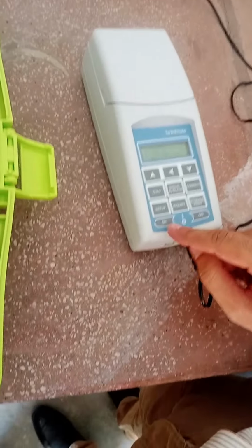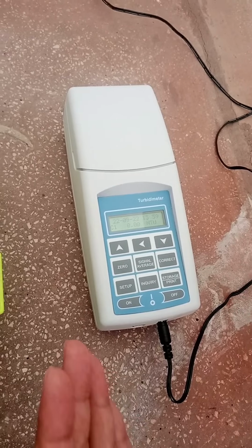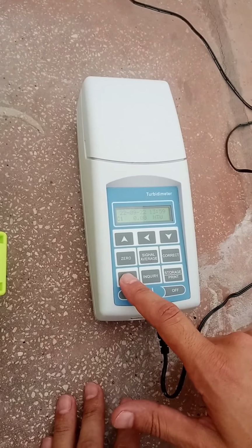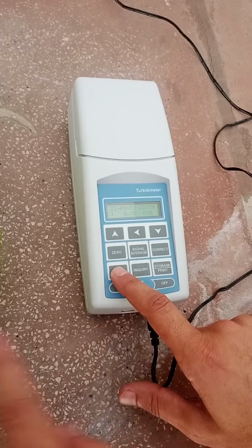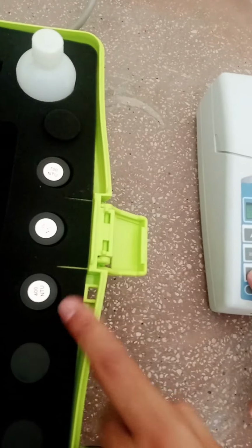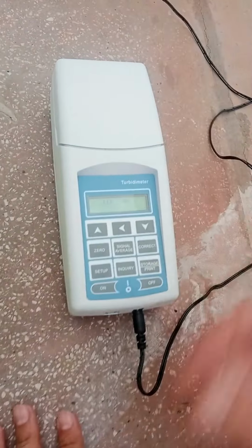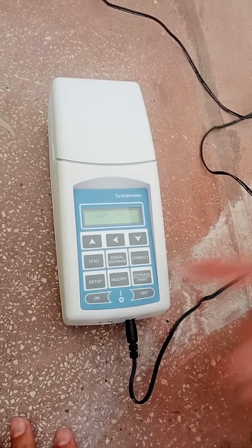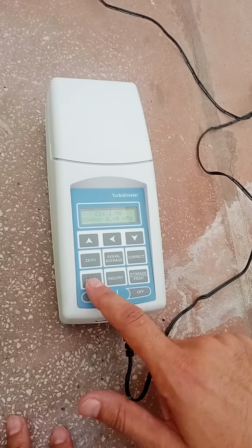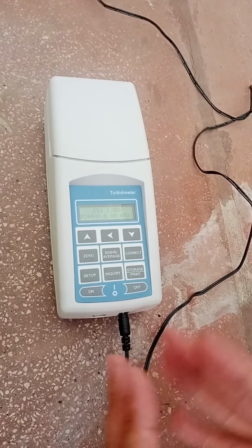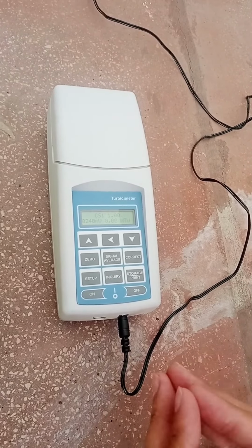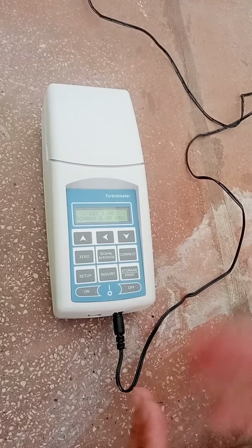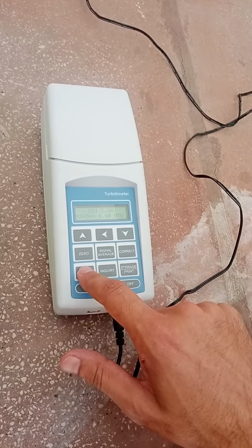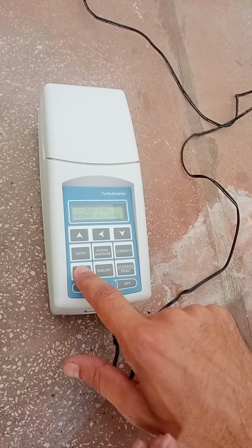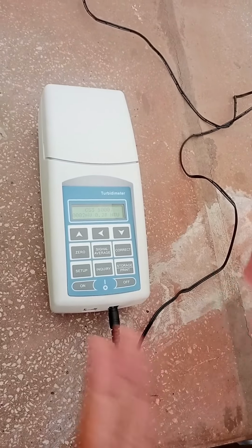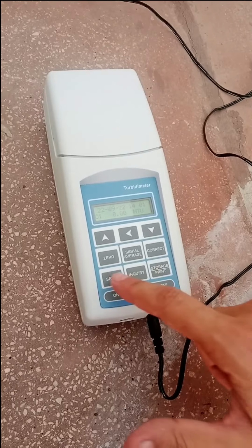Yes, that's correct. The first thing is we will go to the calibration mode, and we will calibrate our machine using the 400 NTU sample. This is the locking code; it is 000 as given in the manual. You will press it. There are 3 setups. CS1 is from 0 to 10 NTU. CS2 is from 11 to 100 NTU, and CS3 is from 101 to 1000 NTU. We are now in CS1.